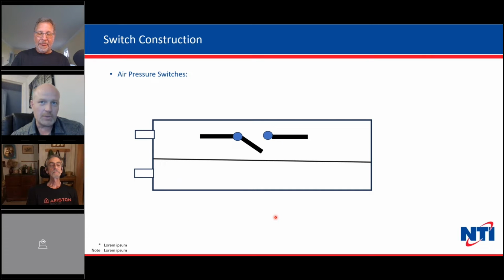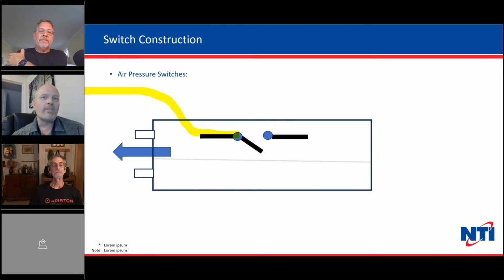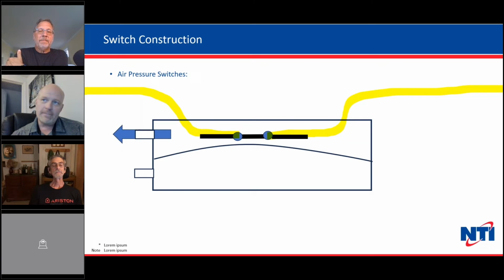So this is your basic air switch. Again, it's got a rubber diaphragm in the middle. It's got a set of switch contacts at the top or the bottom. There's actually a spring in there as well. And the way these are intended to work is if you get enough suction on the top port or enough pressure on the bottom port, you activate the switch. So if we suck on the top, electricity passes through.